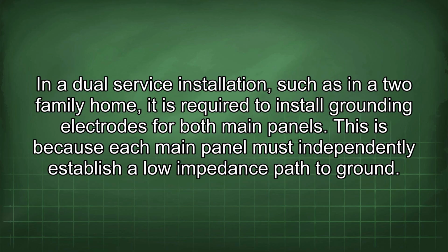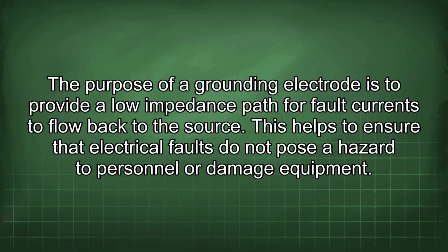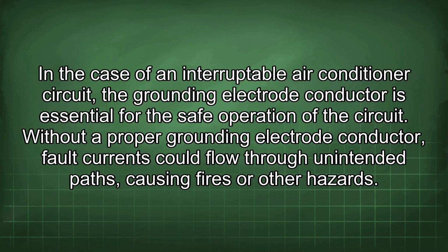Code. In a dual-service installation, such as in a two-family home, it is required to install grounding electrodes for both main panels. This is because each main panel must independently establish a low-impedance path to ground. The purpose of a grounding electrode is to provide a low-impedance path for fault currents to flow back to the source. This helps to ensure that electrical faults do not pose a hazard to personnel or damage equipment. In the case of an interruptible air conditioner circuit, the grounding electrode conductor is essential for the safe operation of the circuit. Without a proper grounding electrode conductor, fault currents could flow through unintended paths, causing fires or other hazards.